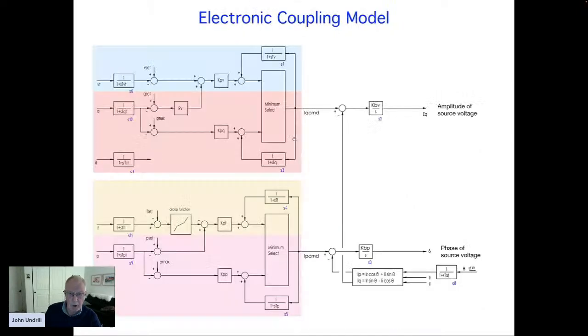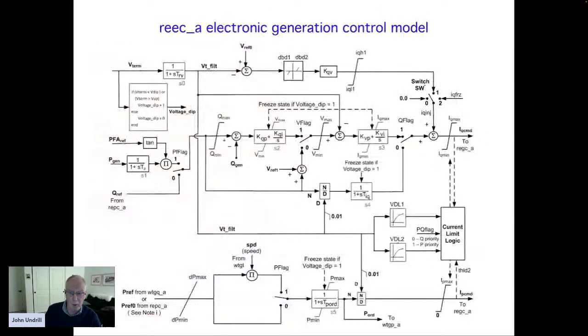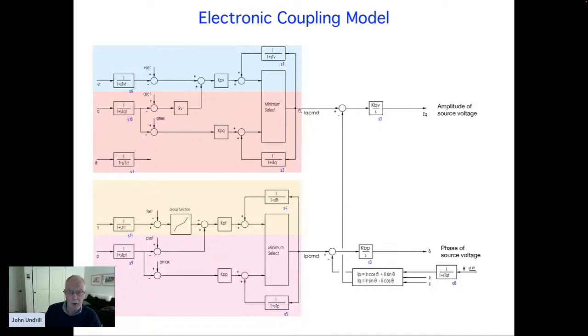I tend to simplify that diagram and rearrange it like this, so that I have an inverter, which is an electronic device. It can be controlled to control voltage, so it measures voltage and compares voltage with a set point. It can be operated with a droop, and the reciprocal of this gain gives me the droop of the drooping relationship, which goes down from speed load reference up here across the page to a reduced frequency at high output.